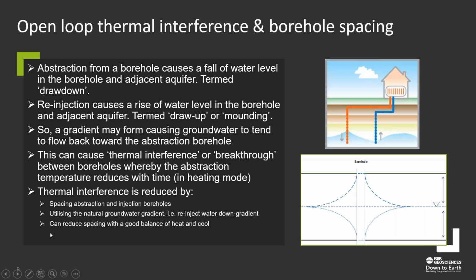The other thing you can do to make it really efficient is have a good balance of heating and cooling, since you can run them both at the same time, or even seasonally run it in one direction or the other. Then the spacing can be much less, so you can fit more in, increasing the overall efficiency of the whole system.